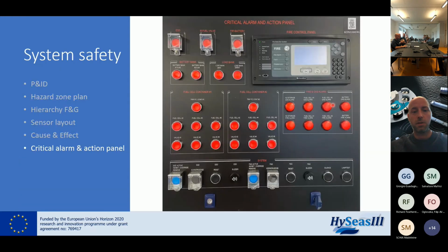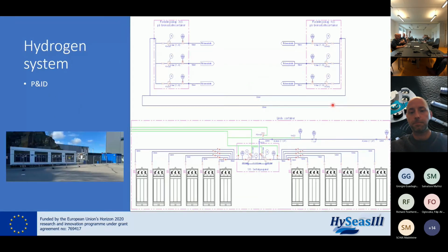Yeah, I will explain it very briefly. This pressure transmitter here is the one where we detected the pressure drop over time, because when we leave the site, we close off the manifold and we close off the fuel supply. So we'll have some meters of hydrogen inside, and we want hydrogen inside that one. We want to keep it not saturated with oxygen or any other gases. When this was pressurized at 15 bars and we left the site closed off, it showed an indication on this one that it dropped approximately 2 bars. So it's actually from a different place than the gasket itself. The gaskets were tight at this stage.